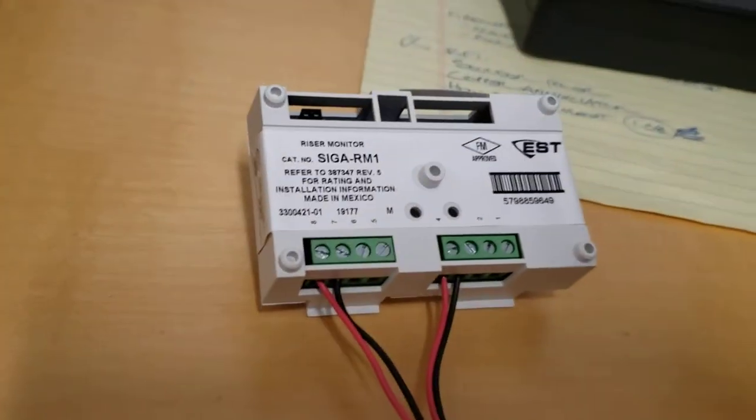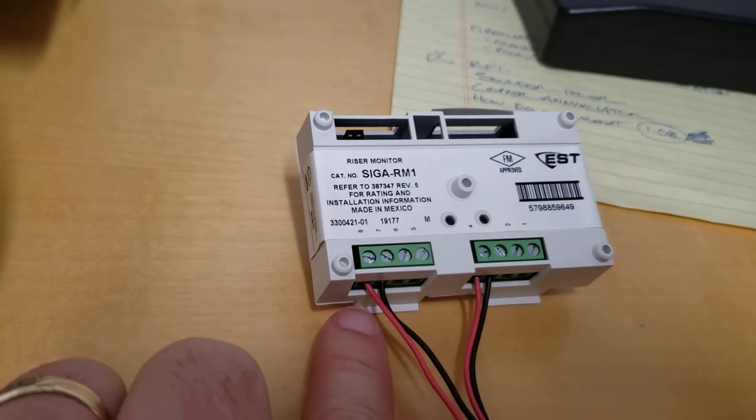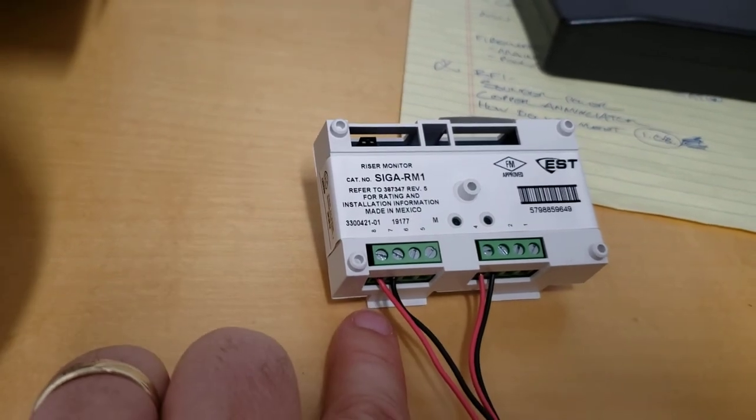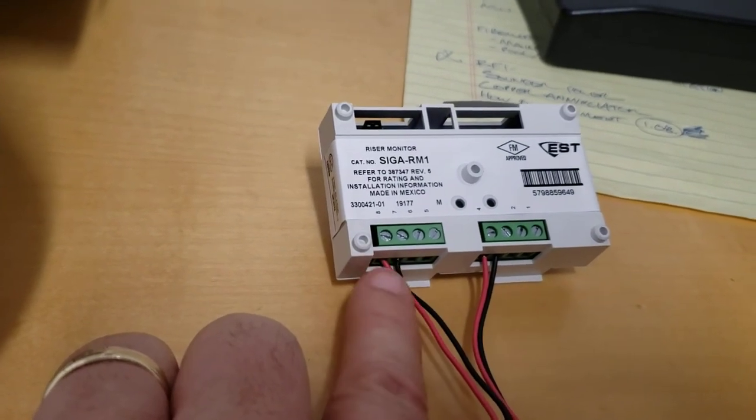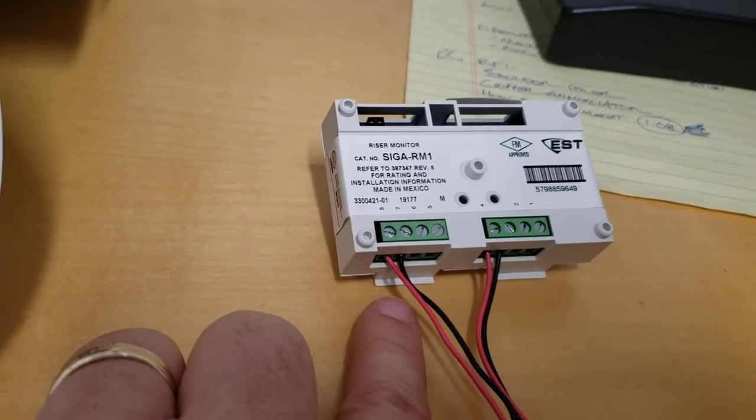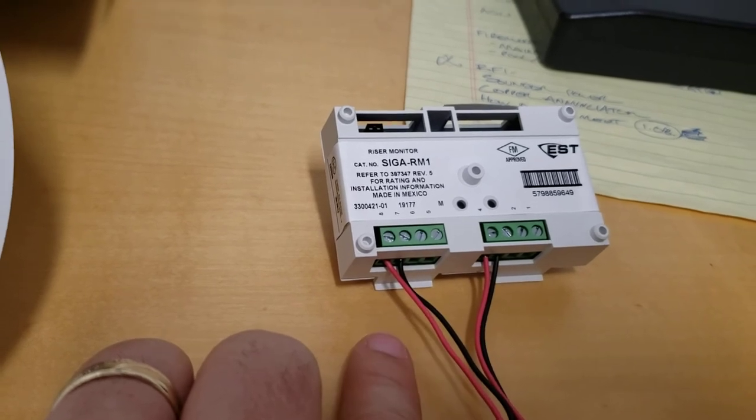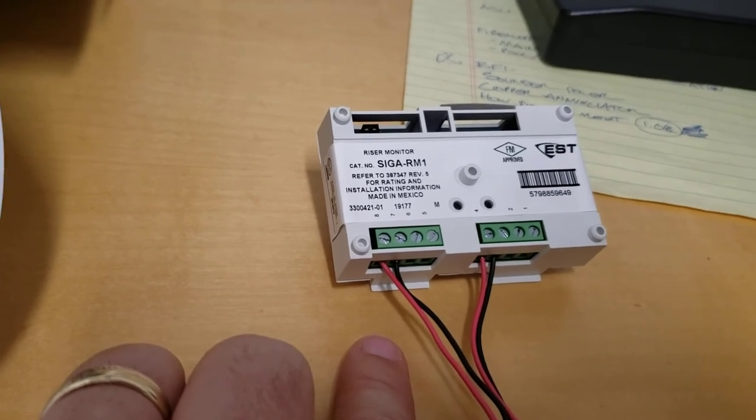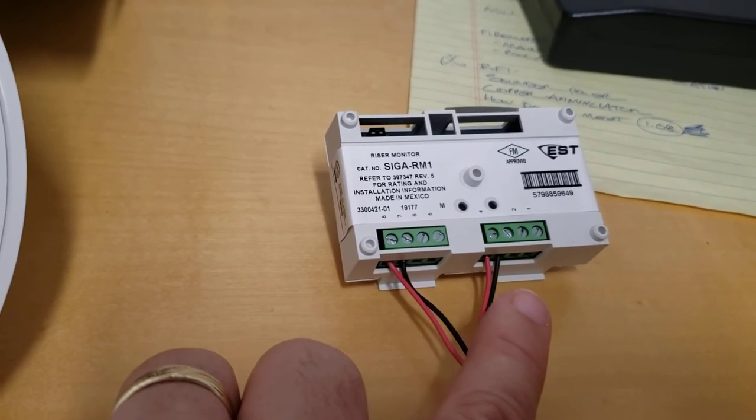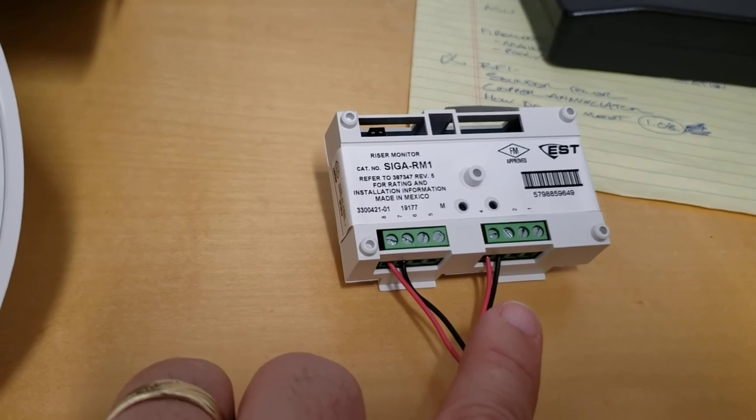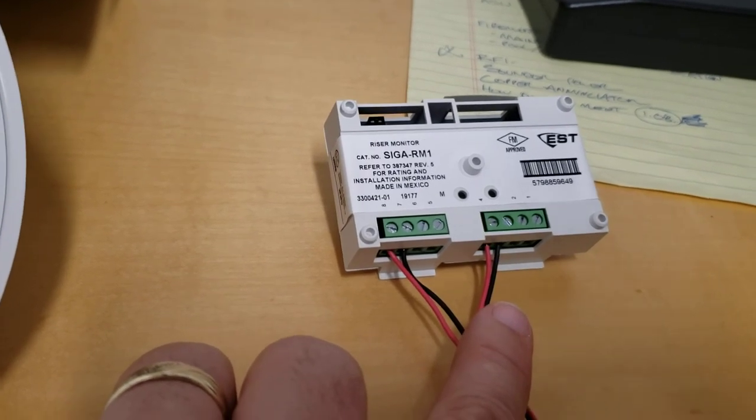The SIGA RM1 is not polarity conscious on the 24 volt riser supervisory circuit here. It doesn't matter but I tend to like to see it wired red and black to match the red and black sequence that you would see on the SLC side.